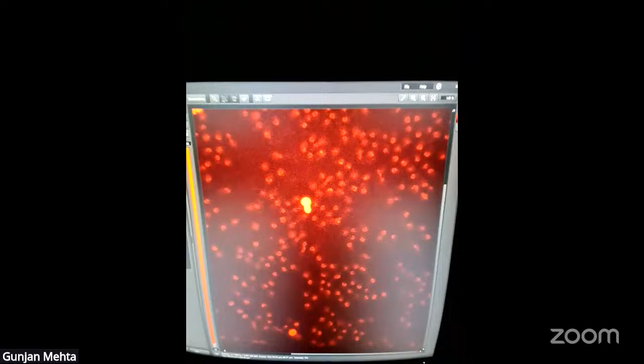So how to define the Z position? In the software module, you have to select what you want to image, whether you want to go for Z stack imaging or time lapse imaging. If you click on time, the software will show you some options for setting the time interval, at what interval you want to take images. If you select Z in the software, it will show you the options to set the Z position: what should be the step size, and how many Z steps you want to collect.